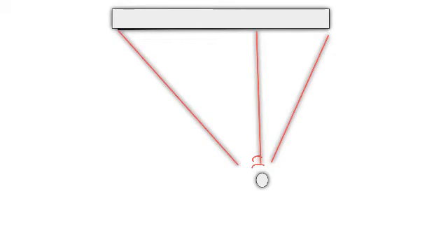And so dynamic receive focusing is able to take these signals that come back from this, which are electrical pulses, and blend them together in the receiver to form one pulse, as if it came from this reflecting structure all at the same time back to the transducer.